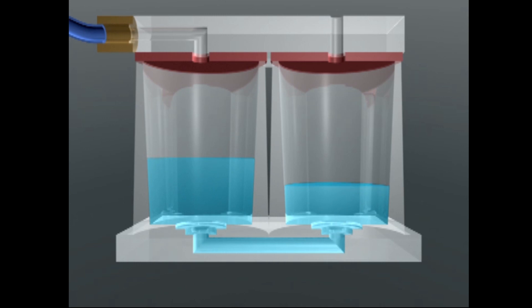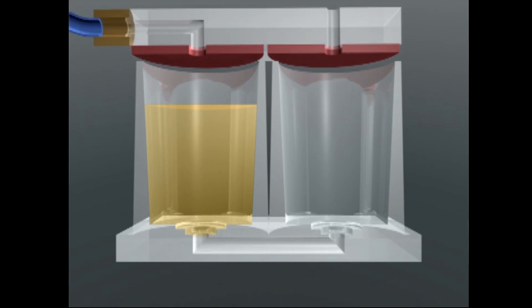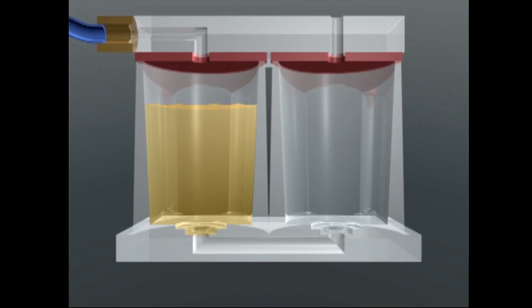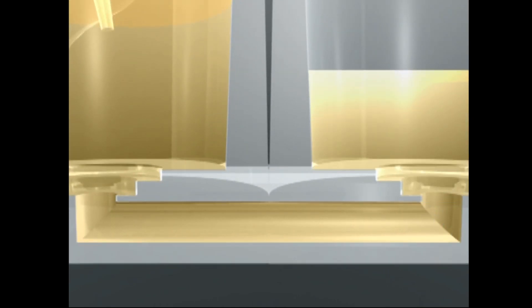In this manner, a variety of cell ligand and cell-cell assays can be performed. Prior to the experiment, coatings such as cell adhesion and extracellular matrix protein molecules can be introduced. The coating is introduced into the inlet well and, using pneumatic pressure, flowed through the channel and allowed to incubate. The excess coating is removed and a washing buffer is introduced. The channel is now coated and ready for the rest of the experiment.